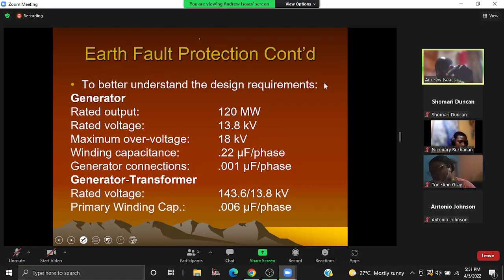Now, I want you to take careful note, the winding capacitance of the generator is several times higher than the others, and for obvious reasons. Because the windings would, of course, be insulated, right? And they are in close proximity. I know this is going off script a bit, but you can use the same principle as to the high capacitance for your cable vis-a-vis your line.